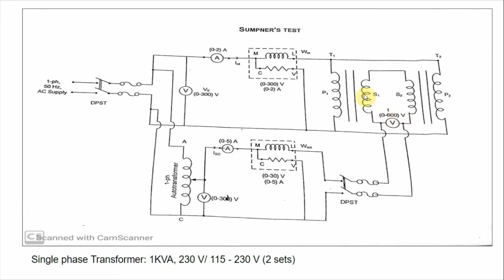If these two transformers are connected in phase opposition, this voltmeter will show 0 reading. If this shows twice the rated voltage or applied voltage, it means that the two secondaries are not connected in phase opposition. The terminals of any one secondary will be interchanged. So again, we will recheck. We will proceed only if this voltmeter shows 0. This is the first precaution that we have to take.